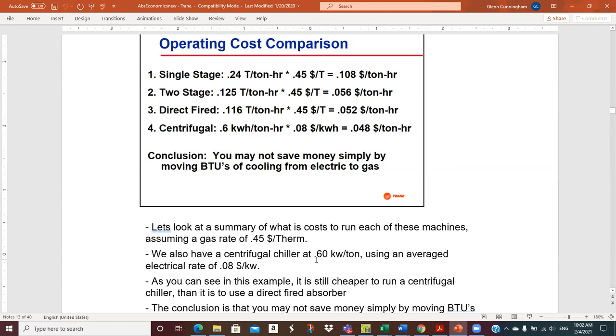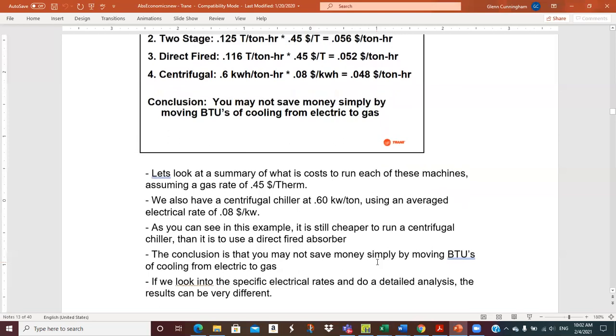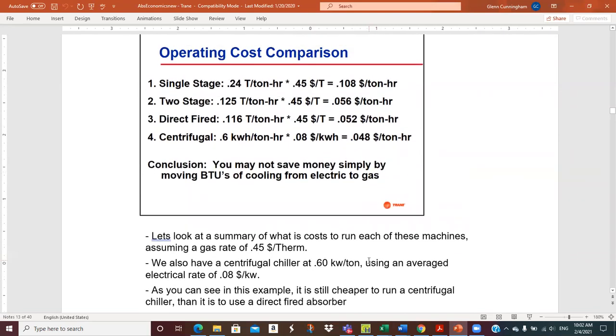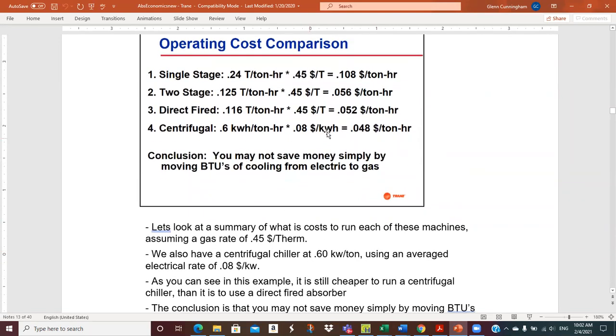Centrifugal has 0.6 kW per ton. I don't know if we calculated that before, and I think that came out to 5.85 on the COP from last class. So the comment here is if we're just moving BTUs from electricity to gas, it may not be such a good idea, given this cost per ton hour.